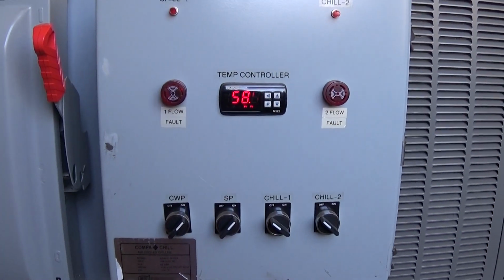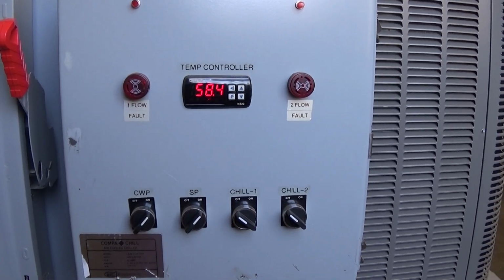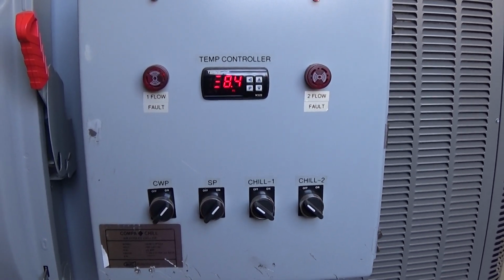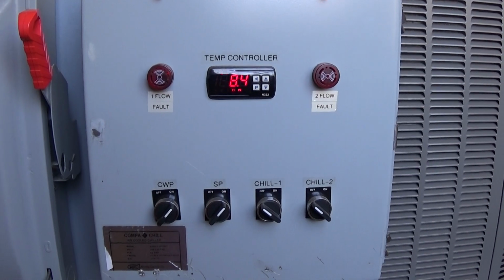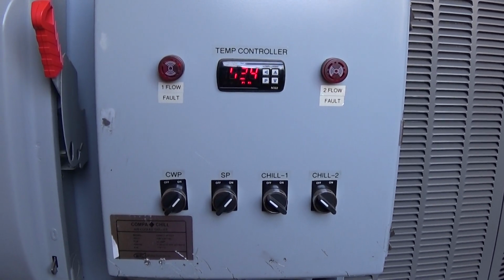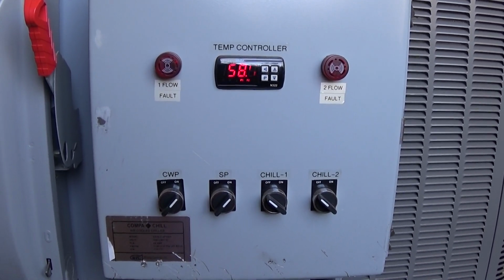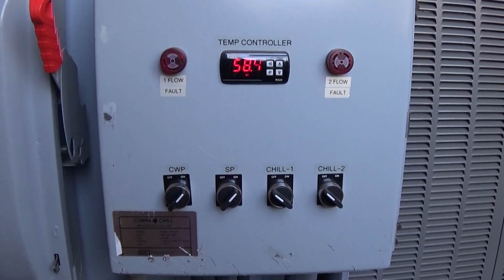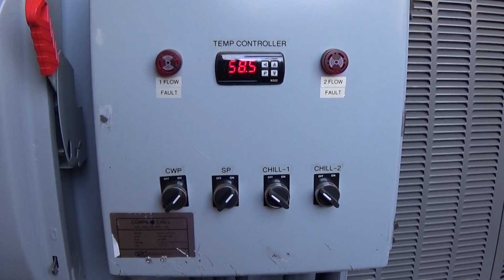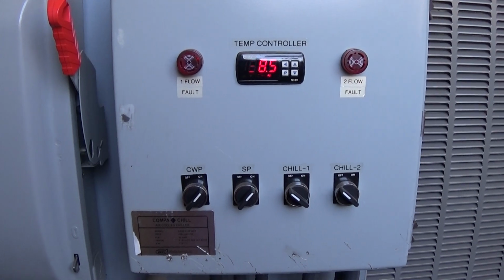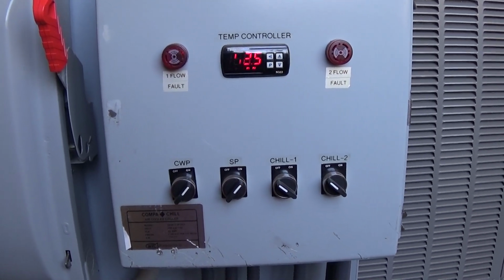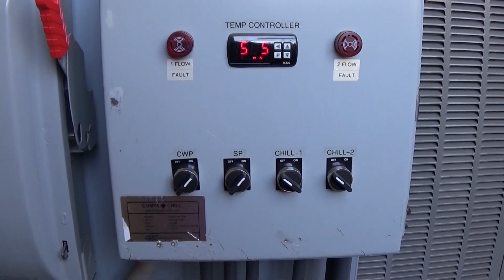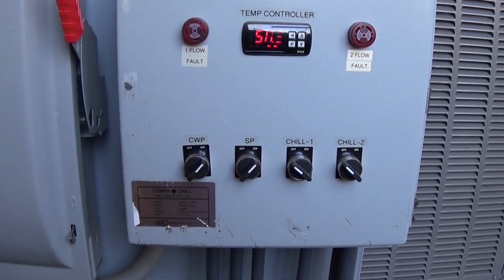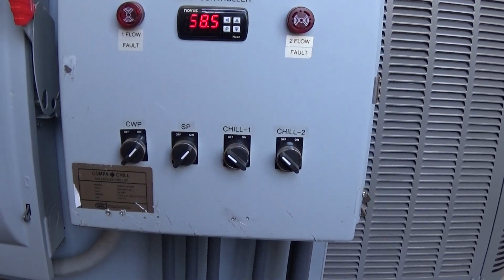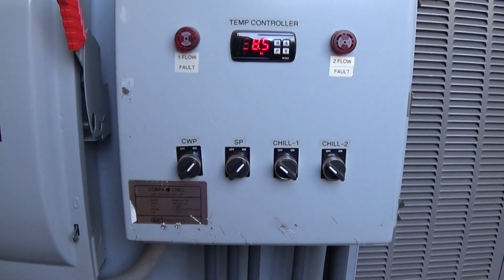That means when circuit 1 reaches its set point, the compressor shuts off, and it's going to wait till it goes 5 degrees above set point before it comes back on again. You want to run with the biggest differential possible that you can get away with, because that is what minimizes the starts and stops of a compressor. If you set that differential to 1, that thing's going to be going on and off all day long, and that's what beats the hell out of a compressor. Don't have it at differential 1. Try to get away with differential 5 if you can.